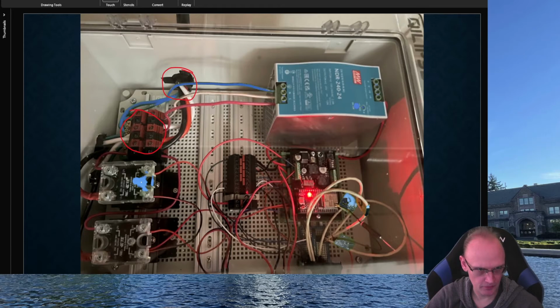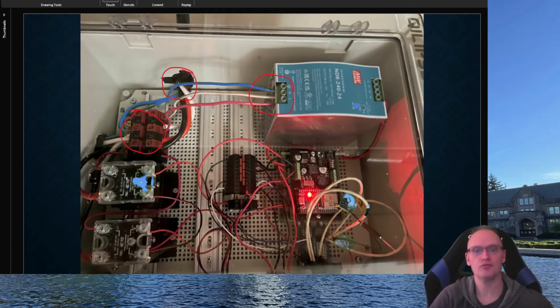Then also coming out of this terminal block, we're feeding the DC power supply here. So for a little historical context, it used to be that 240-volt circuits, the wiring was just 3-wire. You had 2 hots at 120 volts each and the ground. The modern version of a 240-volt circuit actually has 4 wires. You'll have the same 2 hots and ground, but you also have a white neutral. And the addition of this white neutral enables you to wire in a 120-volt component into that 240-volt circuit. So what we're doing here is taking one leg of the 240-volt circuit, which is just 120 volts, and we're also attaching the white neutral and ground. And that enables us to power our 24-volt AC to DC power supply up here.